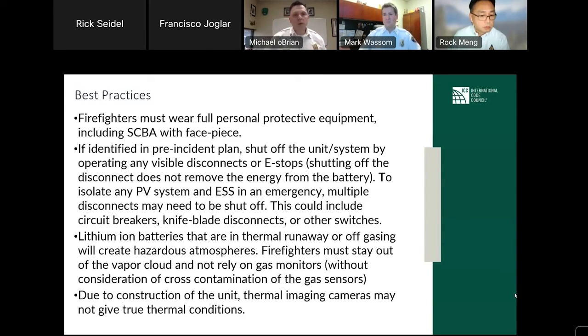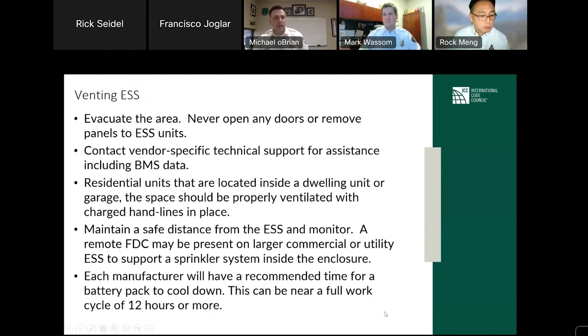Next slide. So when we see something such as a venting ESS, or energy storage system, we want to make sure we start to evacuate the area. So think about where these are being installed. Obviously, a commercial setting indoors is going to be very difficult versus a utility grid on 50 acres, quite removed. And our response will need to be somewhat different. We're going to skip over residential units today, but most of the manufacturers in their emergency response guides start to talk about what the safe distance is. And in that pre-incident plan, some of our work may be supporting something such as a remote fire department connection. It may be protecting exposure.